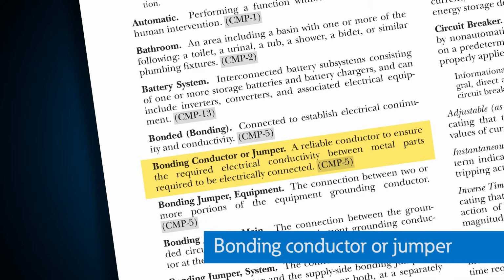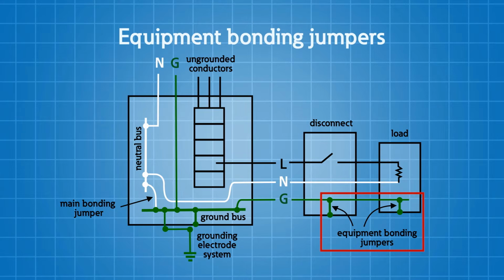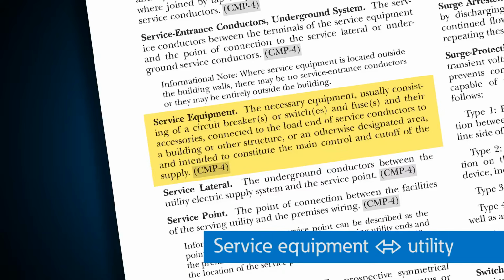Bonding conductors, or what we call jumpers. These are your reliable conductors to ensure the required electrical conductivity between metal parts required to be electrically connected together. Your service equipment, this is where your utility is connecting into the power distribution system. And in this equipment is where we're going to define some very important bonding jumpers.